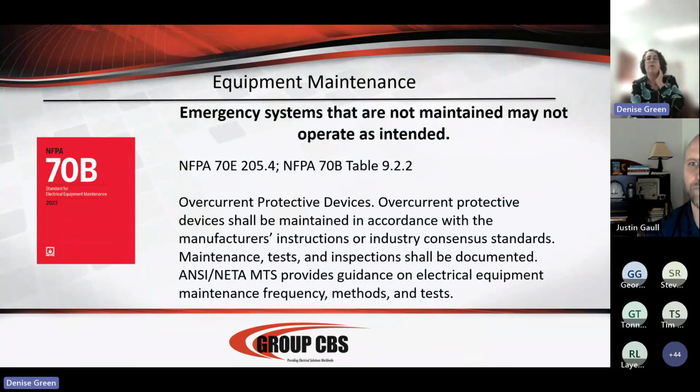So if you have a breaker that is supposed to trip in, for example, 0.143 seconds at 8,000 amps, the calorie label on the door says that it's 2.4 calories, and this is the PPE that you need to wear, and this is the hazard distance and all of that. If that same device doesn't operate for 2 seconds, now you're at 30 calories.